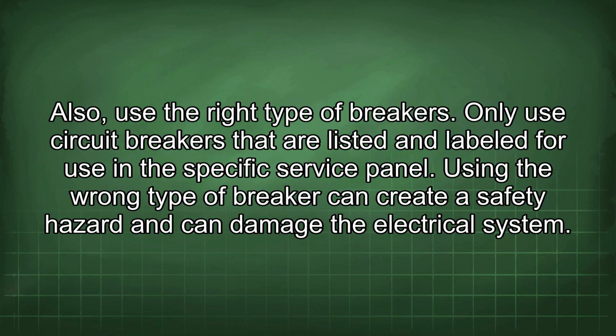Also, use the right type of breakers. Only use circuit breakers that are listed and labeled for use in the specific service panel. Using the wrong type of breaker can create a safety hazard and can damage the electrical system.